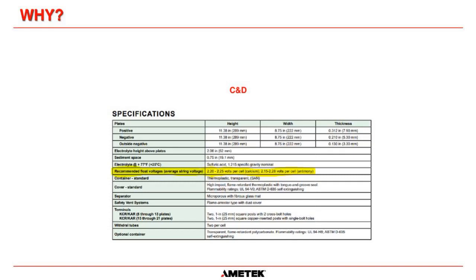Okay, for a vented lead acid cell, the only thing it's going to do is boil off a little bit more water, and you're going to have to top it up a bit more often. It can, in theory, if you did it every week, you're going to be overcharging the battery, so it could cause minor corrosion on the plates, but it's not going to be excessive. Okay. Once again, David, I'll ask my battery expert about mitigating acid stratification.